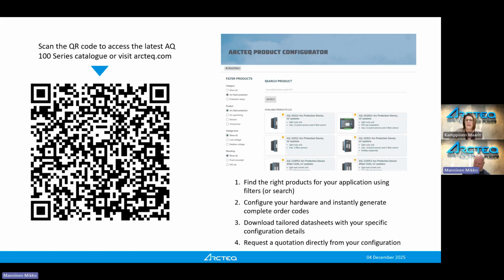Does a Rogowski around cables also extend the current detection zone to include incoming cable terminations within the current zone? Yes, the installation location of the Rogowski is a good point. If I understand correctly, the Rogowski is much easier to install for larger zones, whereas current transformers are typically always after the cable termination or bus duct termination. Rogowskis are a bit more flexible, with 4 to 6 meters of cable from the Rogowski, and they can even include the cable connection zone, which is not typically used in our protection. Was that the question, if I understood correctly?